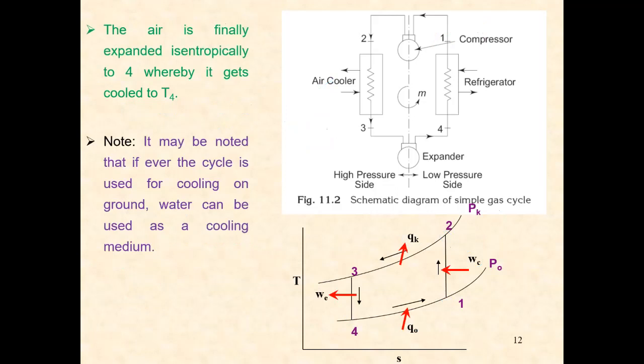To summarize the complete cycle: process 1 to 2 is reversible adiabatic compression; process 2 to 3 is heat rejection in the air cooler; process 3 to 4 is reversible adiabatic expansion in the expander; and process 4 to 1 is heat transfer in the refrigerator.